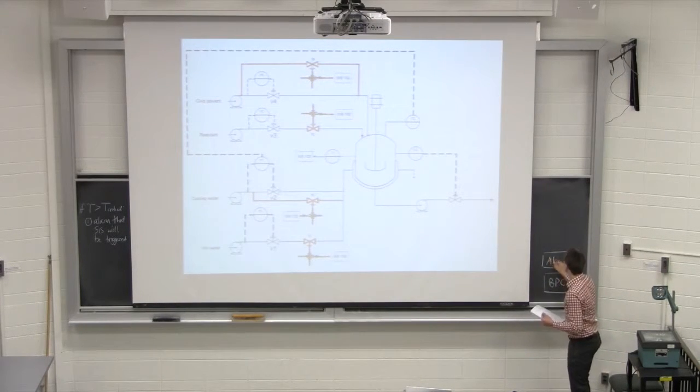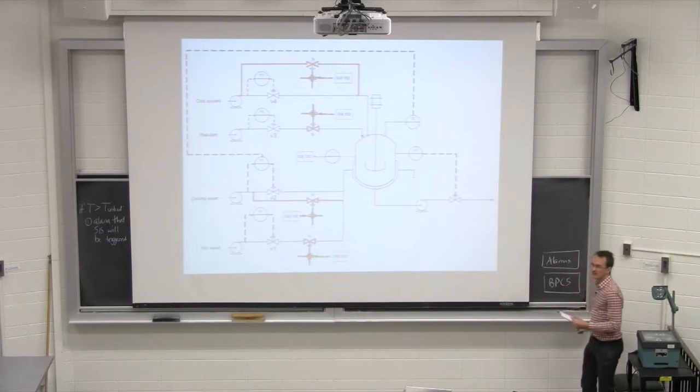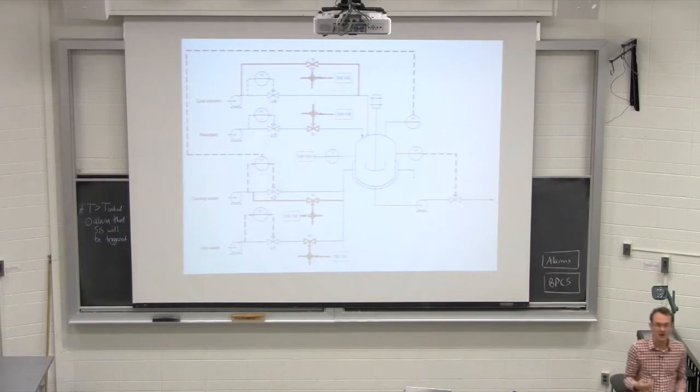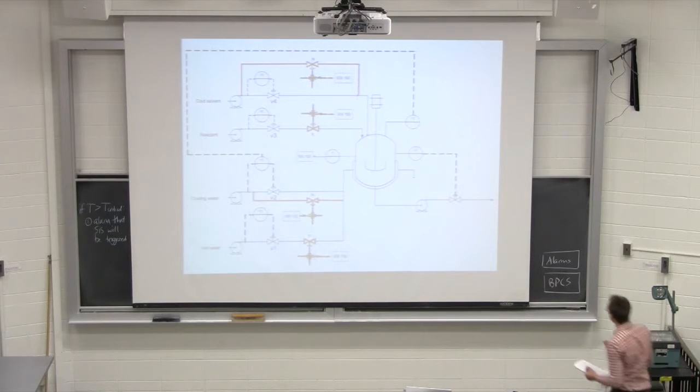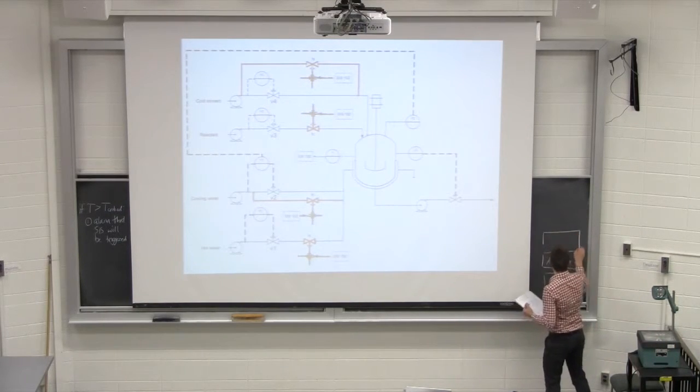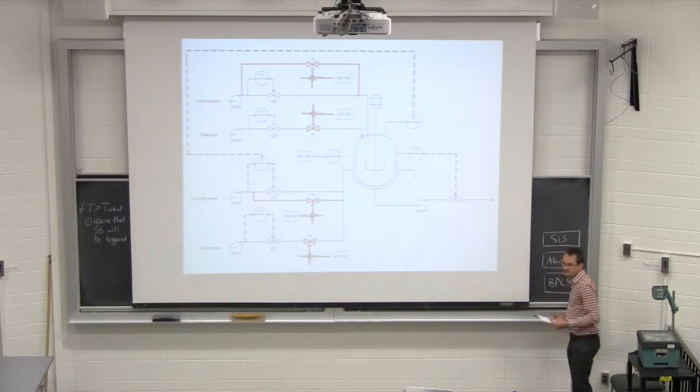The alarm goes to the operators to tell them that the temperature is unsafe, and if the operators have ignored the alarm or are not able to get that temperature in control, then we resort to an automated system which will try to bring the process to a condition of safe shutdown essentially. Okay, so what's in the industry these days is called safe parking of a process.